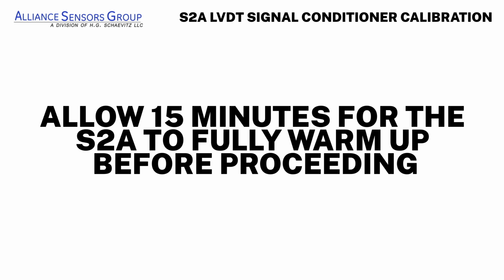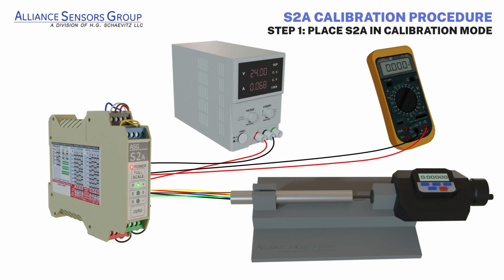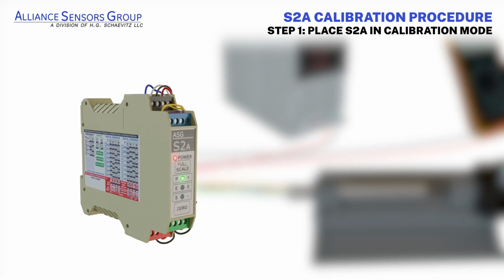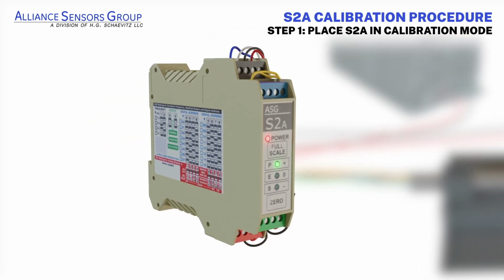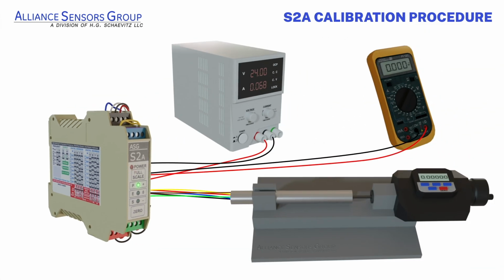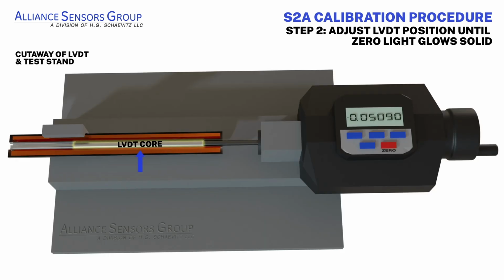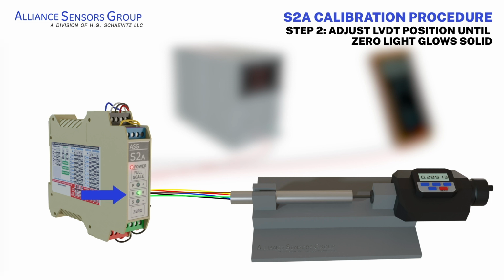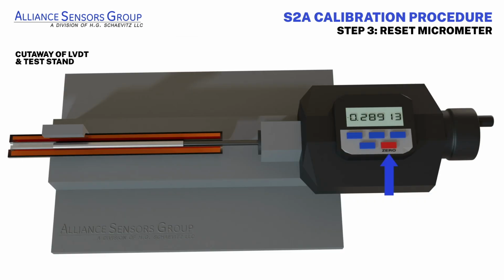With the S2A fully warmed up, we're ready to place the S2A into calibration mode. This is accomplished by pressing both the full scale and 0 buttons simultaneously until the red power LED begins to blink, which indicates the S2A is now in calibration mode. Using the micrometer, adjust the LVDT's core position until the S2A's 0 indicator LED glows solid. This is the null point of the LVDT where the core is at the center of its stroke. Now reset the digital micrometer readout to 0.